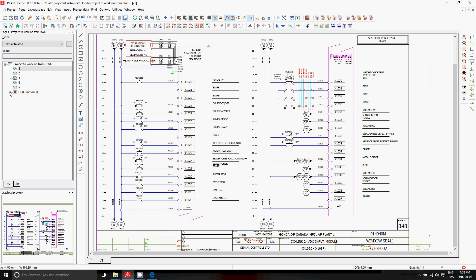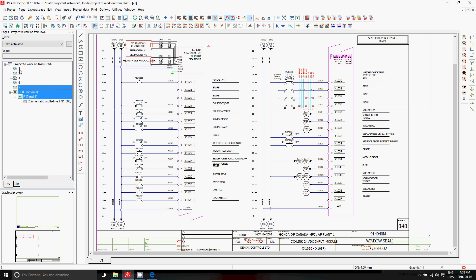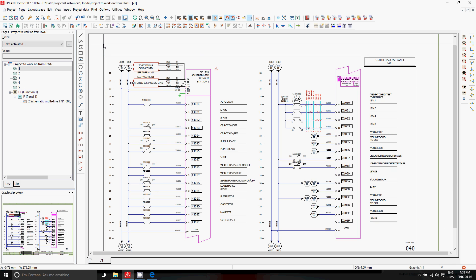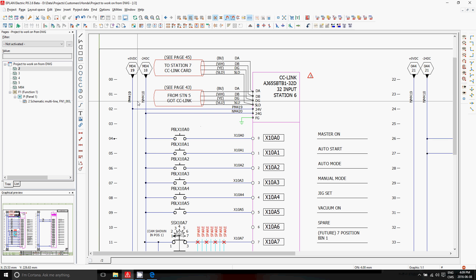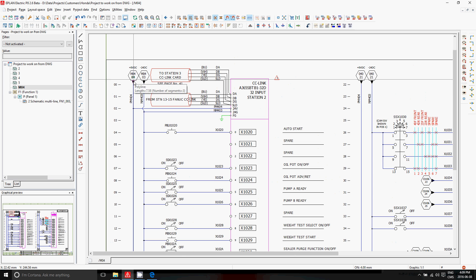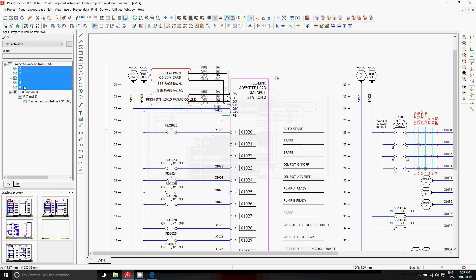Here we can say let's put them as they are — page one, two, three, four, five, six — just to see what happens. And you can see I have my page. Looks good. Now I want to renumber these pages because if I zoom in here, I have a cross-reference that says M04, so this page should actually be named M04. I have to do some reworking because when I imported them, that information was missing. We actually have two M04s, which is a little bit strange. So I'm going to use the renumber feature — start at page 10 and go up from there. And I'm going to move these pages inside my structure so they are moved in that structure and I can now use them as usual.